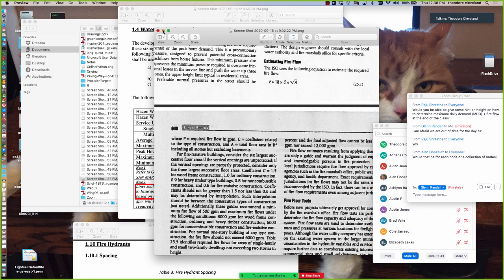Later on, when we build the simulator model, we're going to want to figure out which two nodes matter the most. And you would do that by activating the fire flow sequentially at node pairs based on topography. Is it worse if it's the nodes at the 70-foot elevation, or is it worse if it's the nodes at the 50-foot elevation? That's the level of detail you need to go to. You only have to try a few node pairs. And then that would give you guidance on what the worst case pressure in the system is going to be. But that's actually coming up for a future thing.